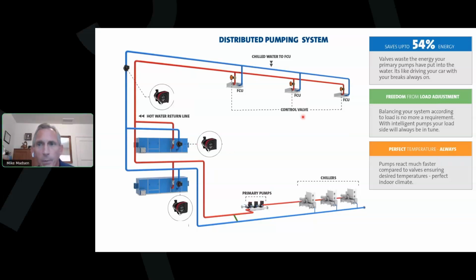So with distributed pumping, energy conservation, how you can save your clients energy, we're going to save at least 54% on pumping energy. I sometimes have the electrical guys sitting in on a lunch and learn, and when I say that you're going to be able to reduce, we had an example, it was a 100 horsepower variable primary system. And I said, well, you're going to have less than 50 horsepower of pumps with distributed pumping. He said, my service requirements are going to go down. So on a new building, that's a good cost savings.